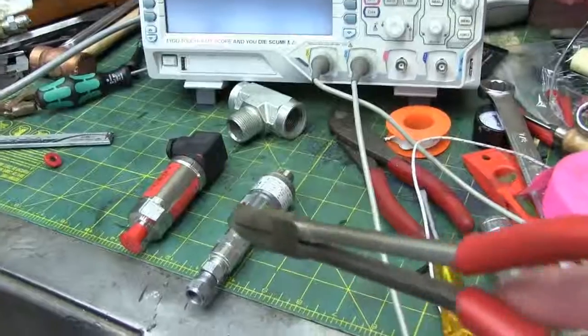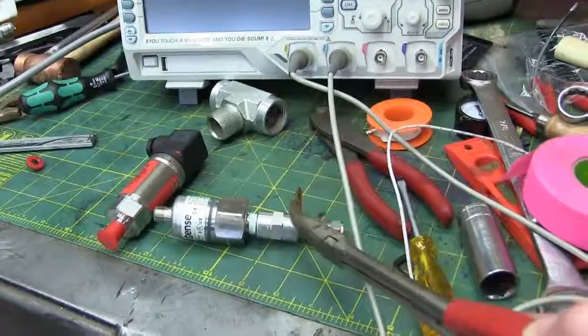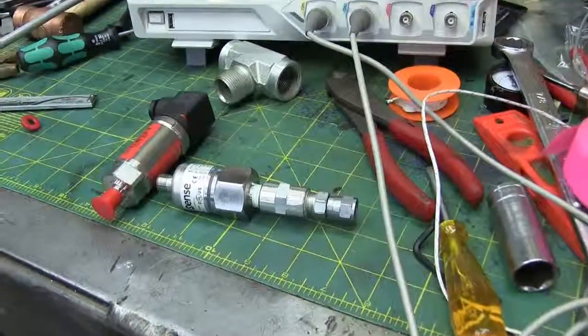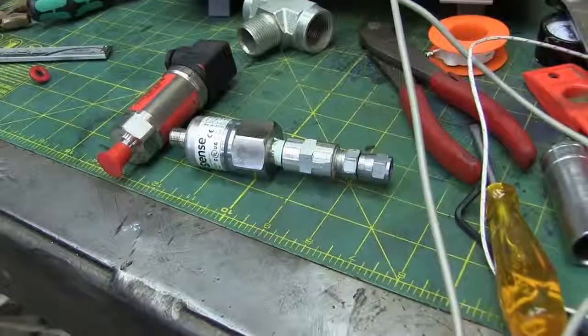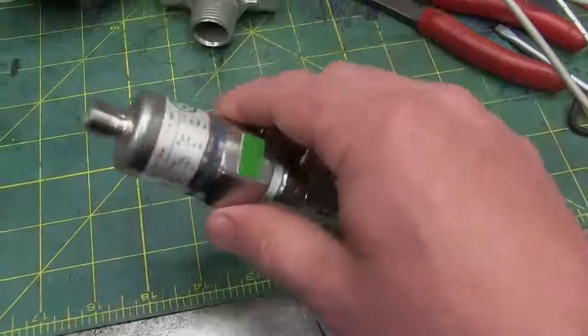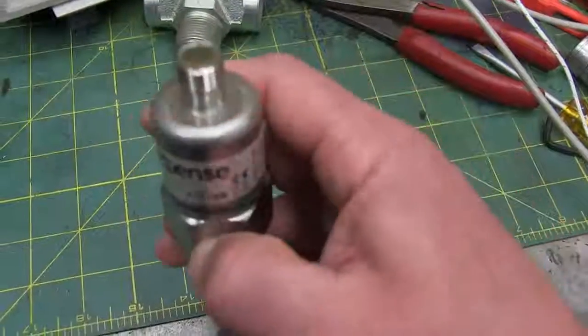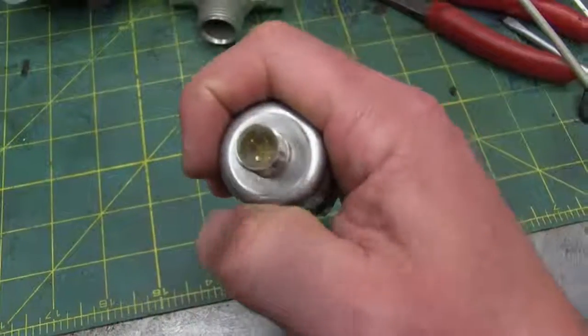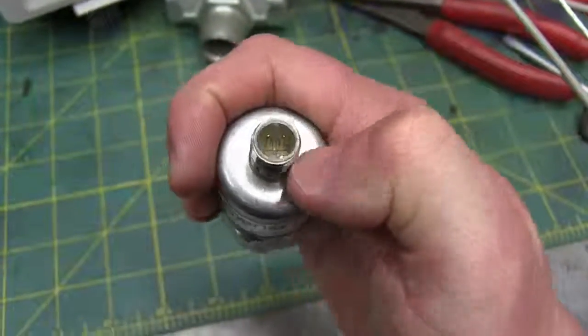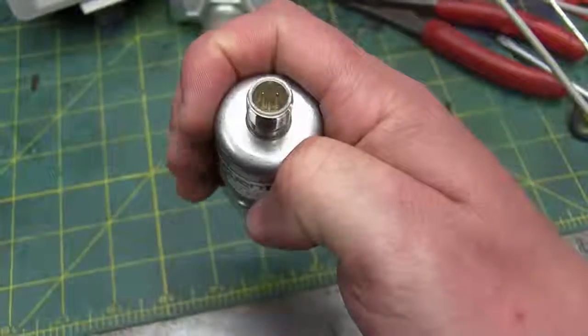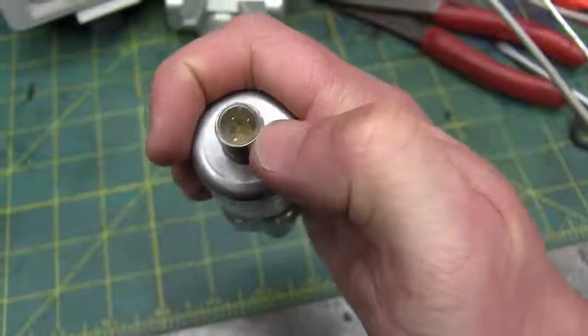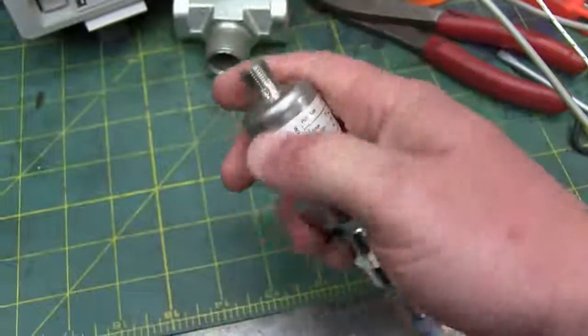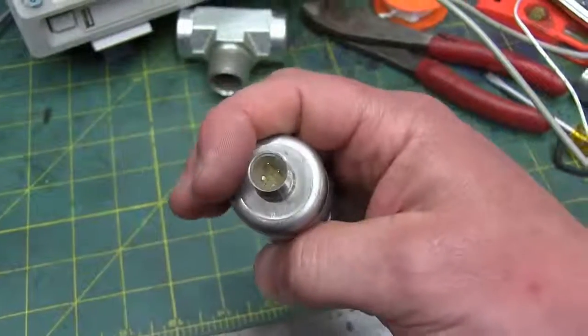However, how are we going to do instrumentation that does not have analog voltage output but has current output, without the need for obfuscation through technical minutiae to make ourselves feel smarter? It's actually quite simple. You see here on these 4 to 20 milliamp devices, there's only 2 pins. 2 pins can't be that complicated to hook up.